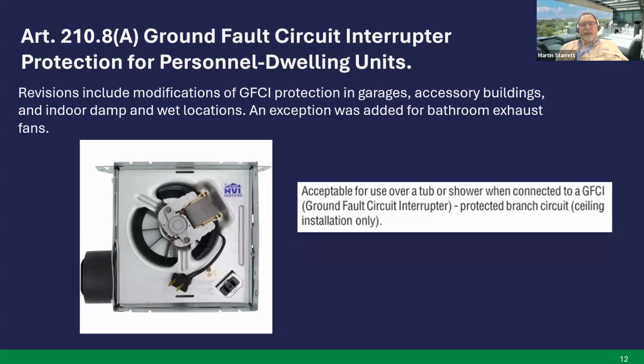But they did add an exception for bathroom exhaust fans. As you know, there's a factory receptacle installed in most bathroom exhaust fans, and the exception says that if that is factory installed, you don't have to have GFCI protection for that receptacle unless the manufacturer tells you. FYI, some manufacturers, if you install these exhaust fans over a tub or a shower, tell you that it has to be connected to a GFCI protected branch circuit installed in the ceiling. But if it's not in those areas and the manufacturer doesn't say it, it does not have to be GFCI protected. Next slide.